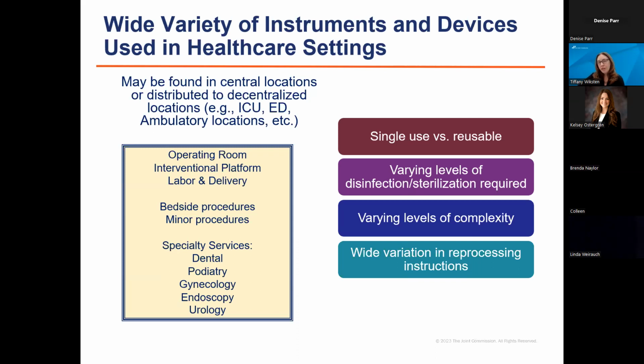When you look at the instruments and devices that you have in your organization, take a look and see, are they single use or reusable? There's varying levels of disinfection or sterilization required. What we're finding recently that seems to be difficult for some organizations to manage are these single use instruments or devices that come with instructions to sterilize them. So the manufacturer is supplying them non-sterile, and they are required to be sterilized prior to their one and only use. So it can be a bit confusing because we think single use shouldn't have instructions for reprocessing, right?